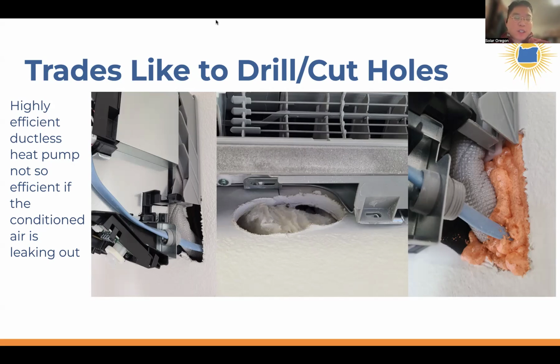One of the ductless heat pumps even had an additional hole in the middle, because the installer thought that's where they wanted to run their line set and electrical connections, and then they found out, oh well, I actually need to move over like a foot and a half. So he left that hole there, hidden behind the ductless heat pump, and we found it with a blower door.